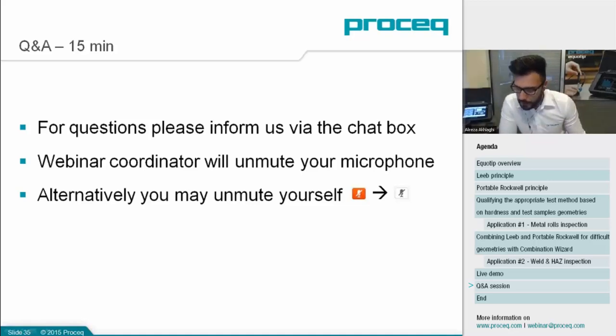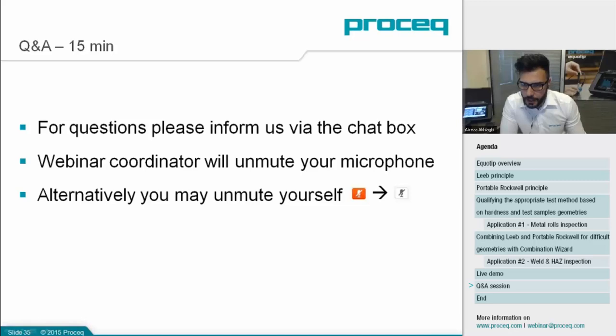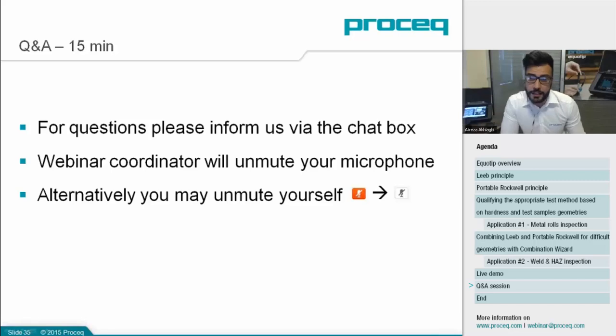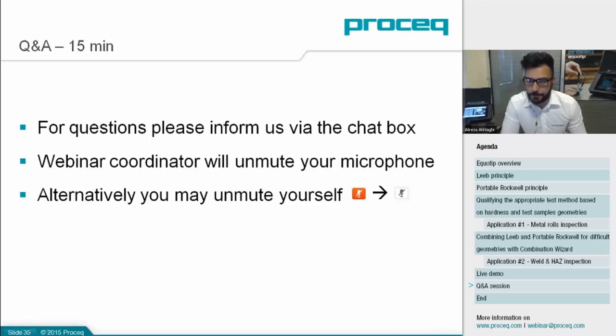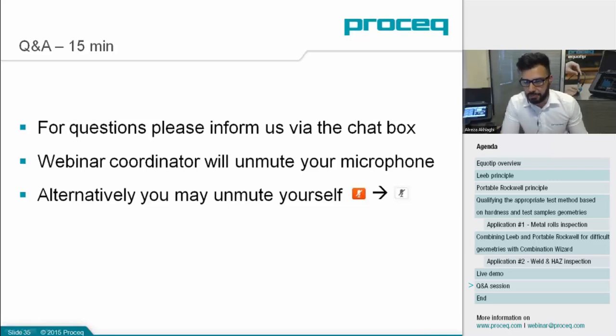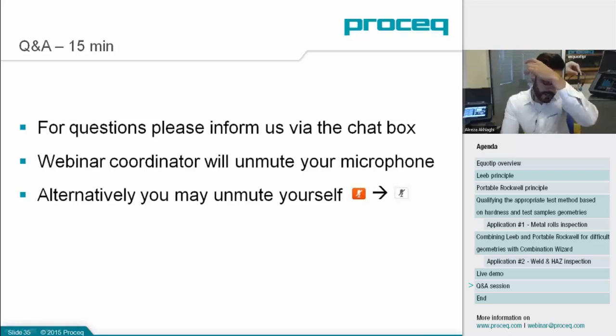Question: will the new UCI probe be used in the combination curve method as well? Absolutely — that's the whole point. You'll be able to use the combined method to correlate both UCI and Leeb to portable Rockwell through indentation hardness. That makes it a very unique device. The platform is already capable of doing that. It's just a matter of connecting your UCI device to the platform and you're ready to go. If you've already invested in Equotip 550, you just connect your UCI probe when it's available and you're all set.